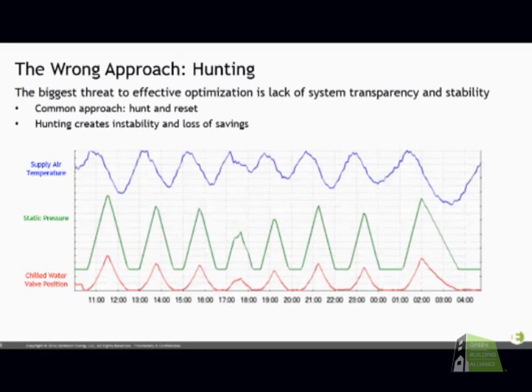So you have this sort of hunting pattern, and this is real data. This isn't something we created. This is from a real site. And that's the problem with just arbitrary set points, where you try to maintain an arbitrary static pressure within the system, an arbitrary chill water position, and then kind of adjust as you go. Because it goes a little bit back to the point that Matt was making before, just looking at an individual component. So if you're just looking at the fan and you're just maintaining a given fan speed based on static pressure, you're not really looking at the whole system because there's multiple things happening all at the same time.